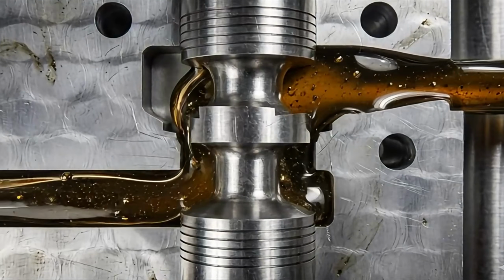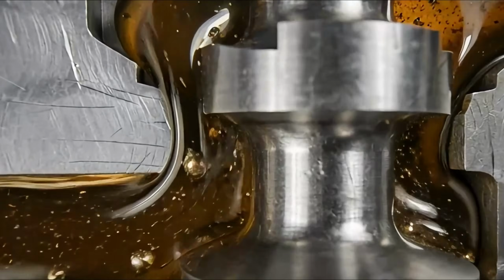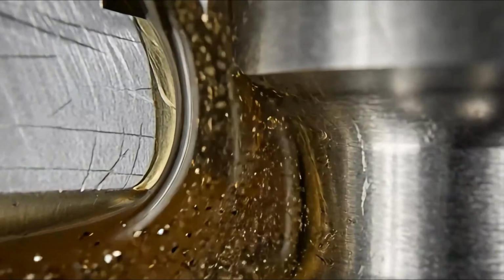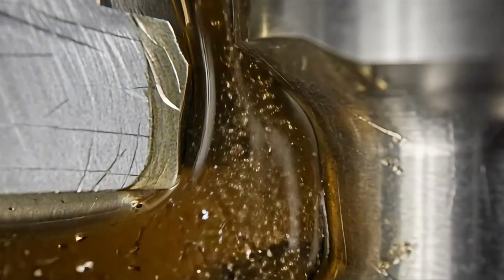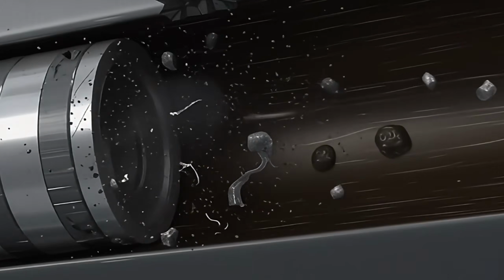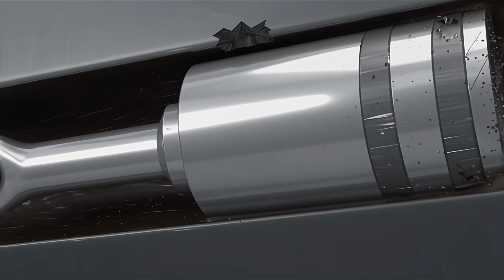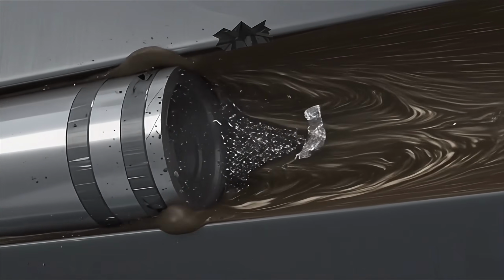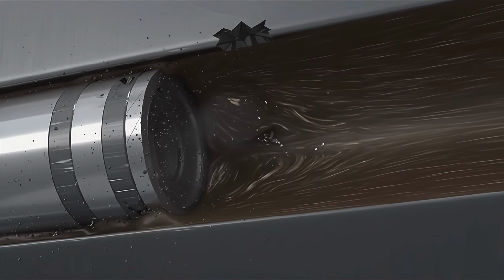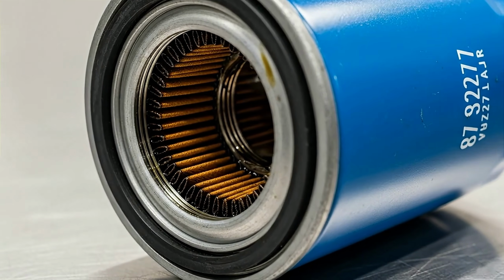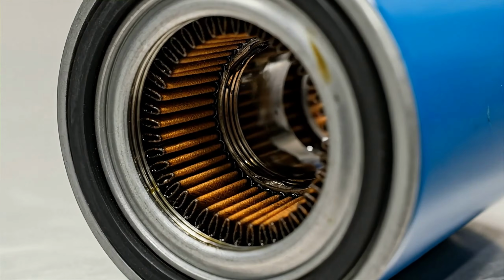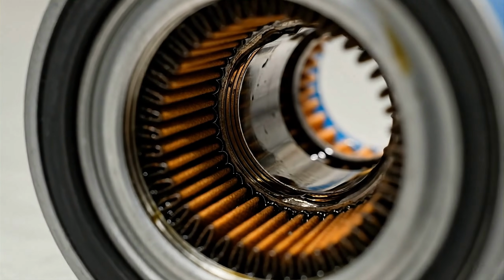in a short time. Inside the hydraulic pump, particles break down. This situation increases wear on all surfaces that are protected only by a thin oil film. Softer particles crumble. Water can damage components even due to cavitation. Over time, all particles become even smaller, and for this reason, it becomes increasingly difficult to capture them with a standard system filter.